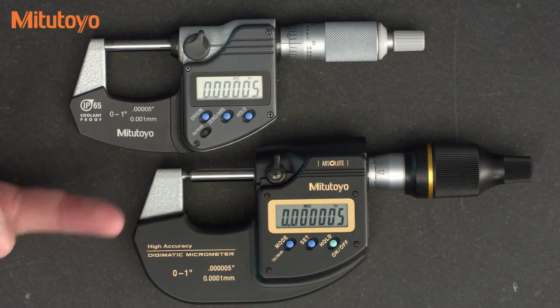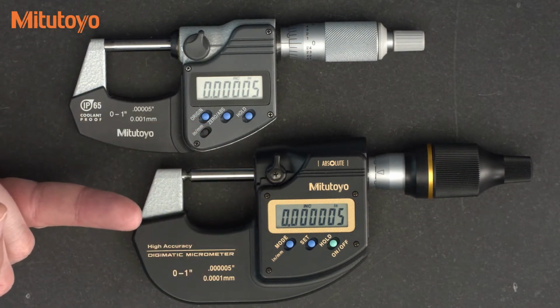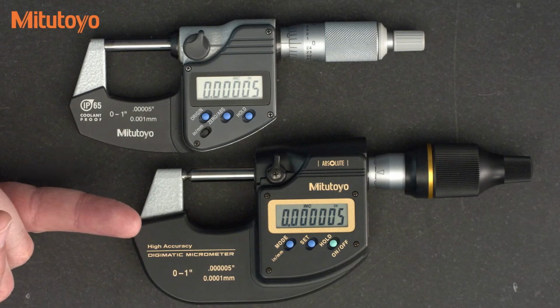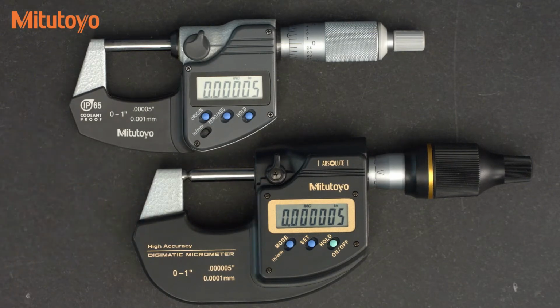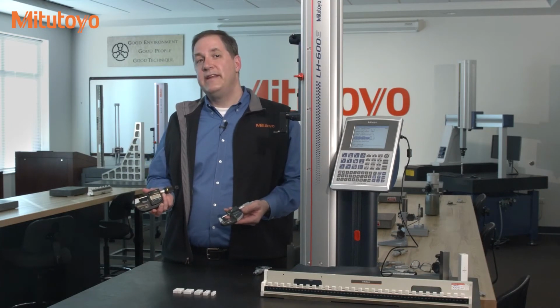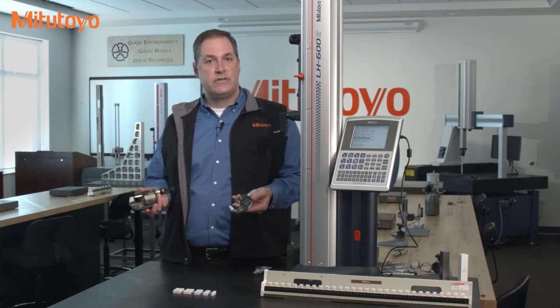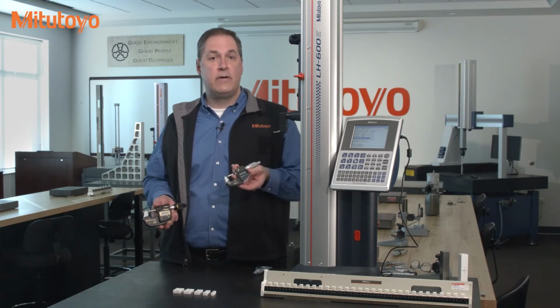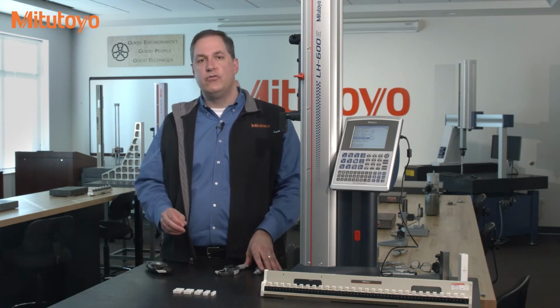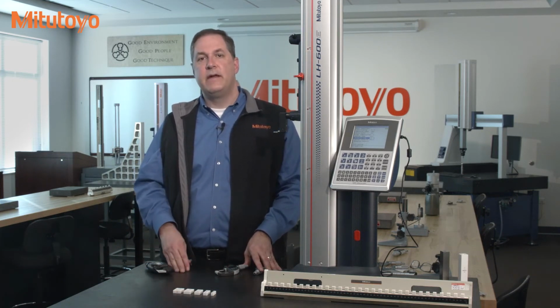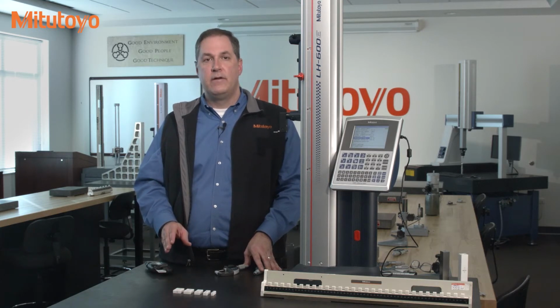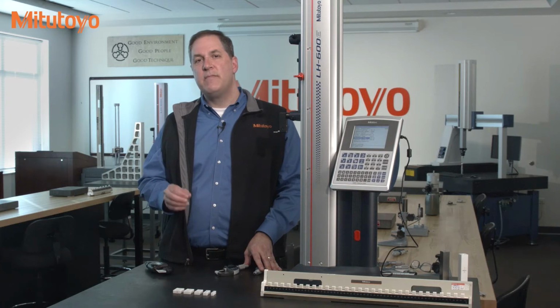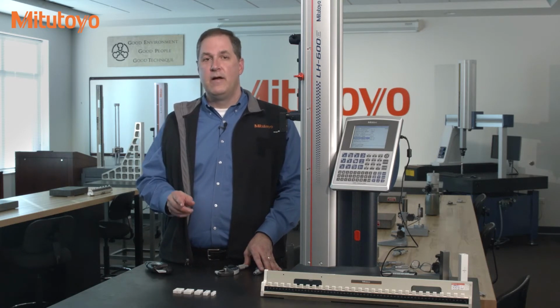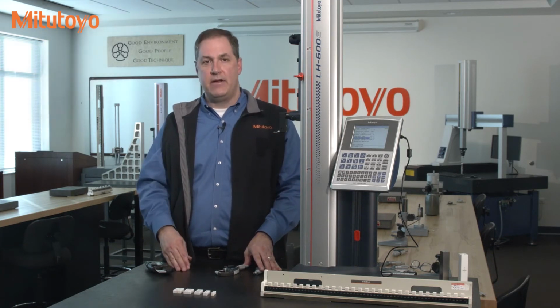And the MDH, between all of those different design features, leads it to have an improved accuracy of just 20 millionths of an inch, or half a micron. The MDH is an outside micrometer. Can't you just calibrate it like any other outside micrometer? In our calibration lab, our calibration technicians do use the same reference standards to calibrate the MDH, just like any other micrometer. And from a distance, the calibration method looks pretty identical. But there's one critical little difference that's so very important to understand.